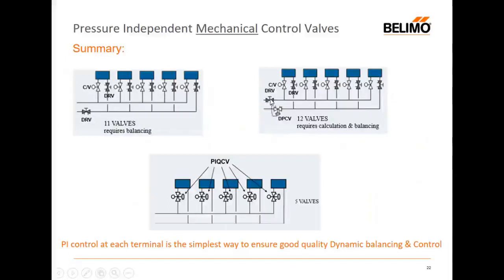the commissioning team know how to set this up, because there has been a tendency, I've seen it myself, where they don't really understand this and they just do a manual balance. And that's a disaster, because this is the valve that should be doing the balancing here. It should be maintaining constant the delta P seen by these control valves to give them some authority. And that really explains the popularity of PI valves, because PI valves do all the differential pressure control on the circuit itself within the valve. So that's as good as it gets.